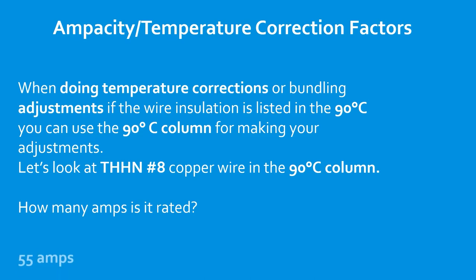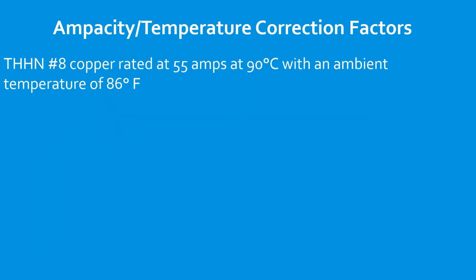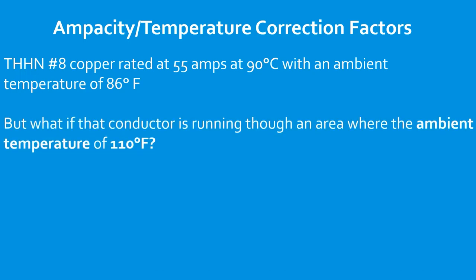So how many amps is it rated for? Number eight copper in the 90°C column is rated for 55 amps. In the 75°C column it's rated for 50 amps, and in the 60°C column it's rated for 40 amps. You'll understand why it's important that the codebook allows us to use the 90°C column before making temperature corrections or bundling adjustments. THHN number eight copper is rated for 55 amps in the 90°C column, but only with an ambient temperature of 86°F.